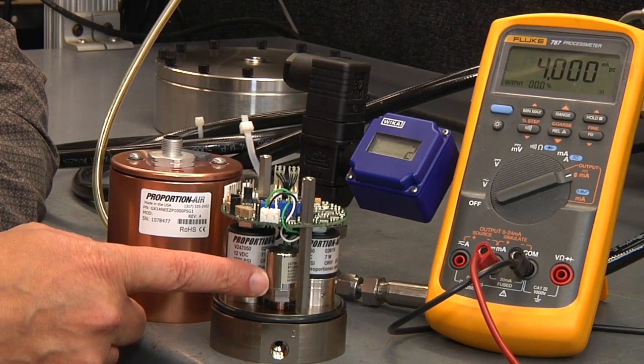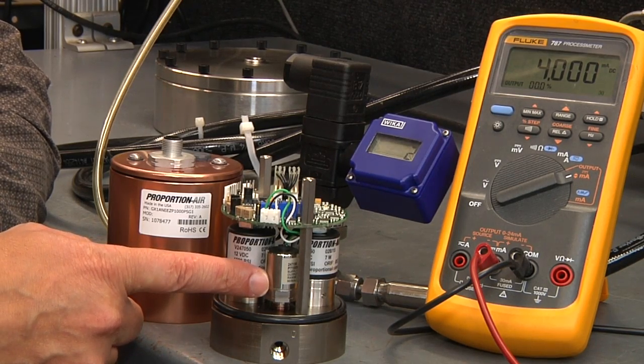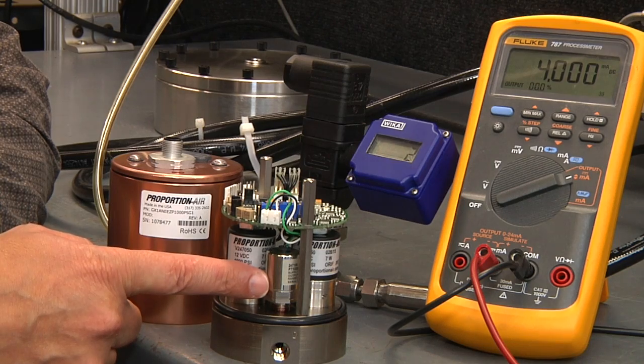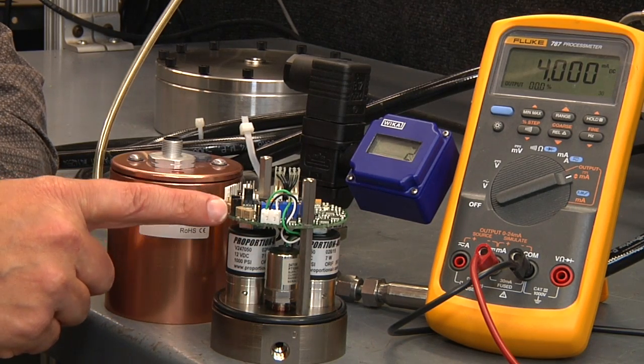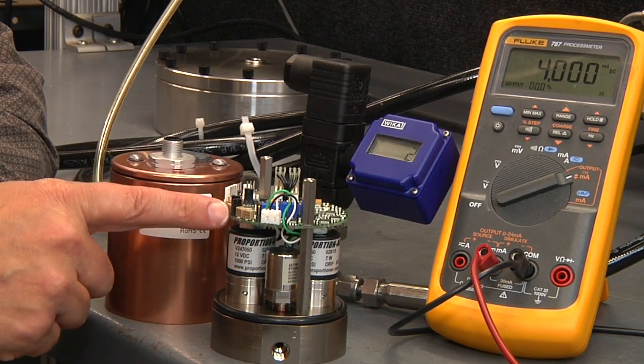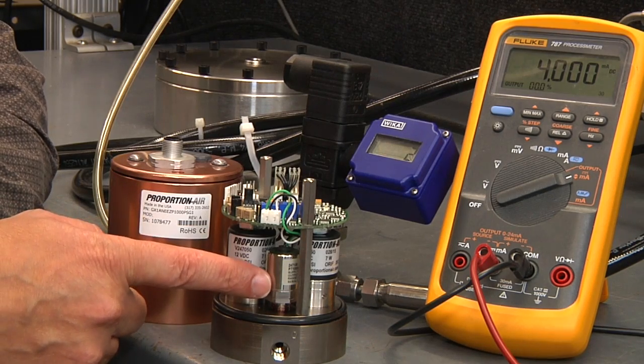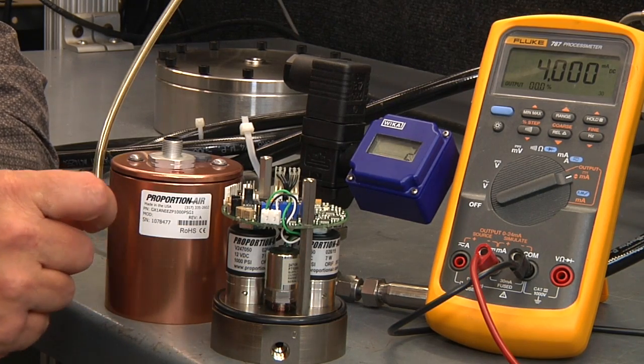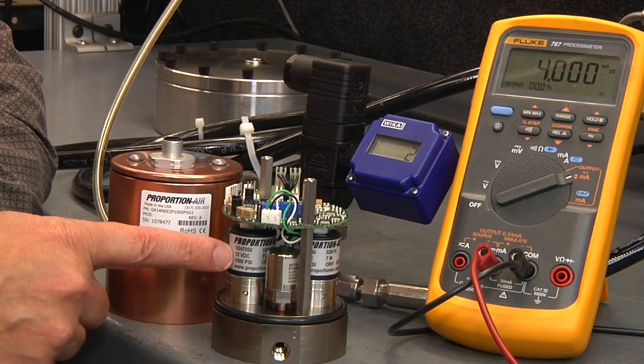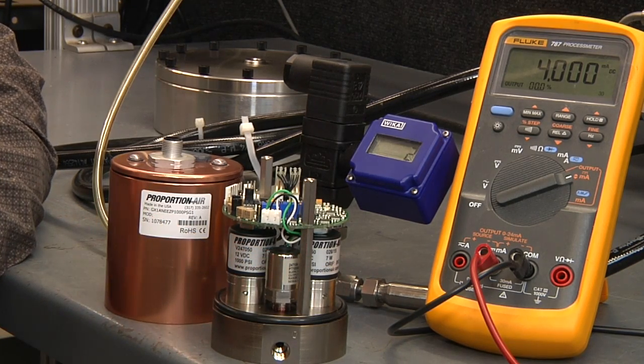This stainless steel pressure transmitter is mounted between the two valves and it measures the system pressure and provides feedback to the circuit board. The circuit compares the pressure to your desired set point and modulates one of the two valves accordingly to set the pressure equal to your command.